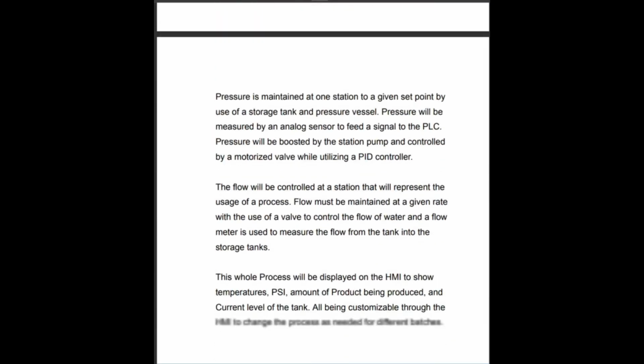Pressure is maintained at one station to a given set point by the use of a storage tank and pressure vessel. Pressure will be measured by the analog sensor to feed the signal to the PLC. Pressure will be boosted by the station pump and controlled by a motorized valve while using a PID controller. The flow will be controlled at a station that will represent the usage of a process. Flow must be maintained at a given rate, which is done with the use of a valve to control the flow of water, and a flow meter is used to measure the flow from the tank into the storage tanks. This whole process will be displayed on the HMI to show temperatures, PSI, amount of product being produced, and the current level of the tank, all being customizable through the HMI to change the process as needed for different batches.